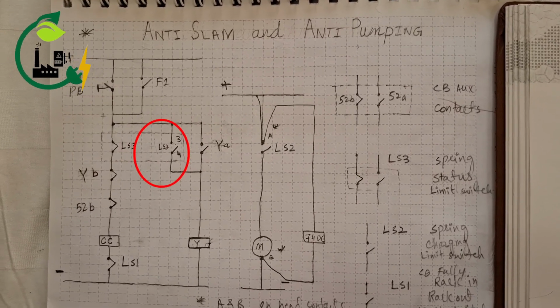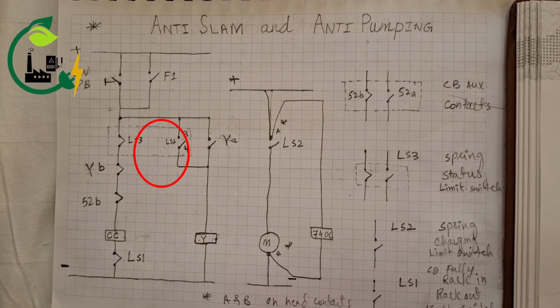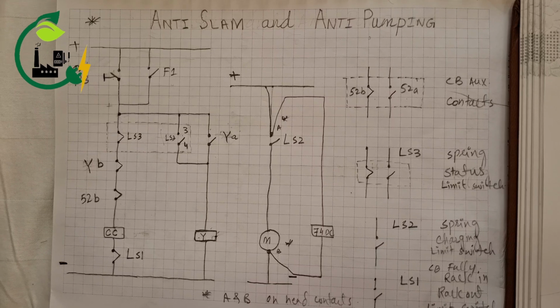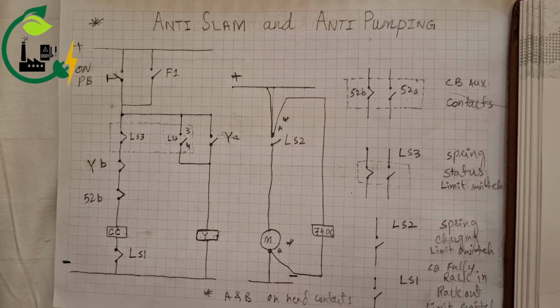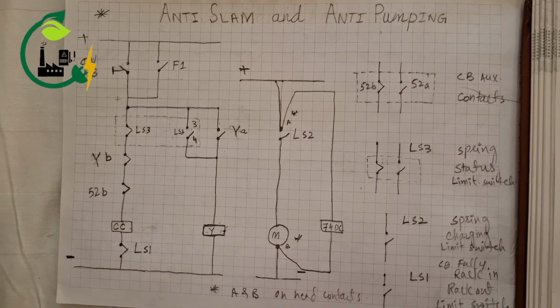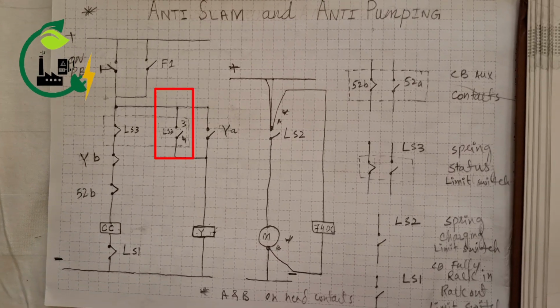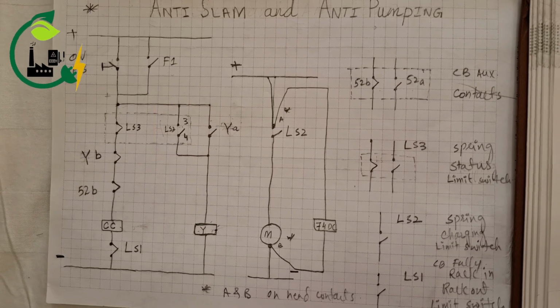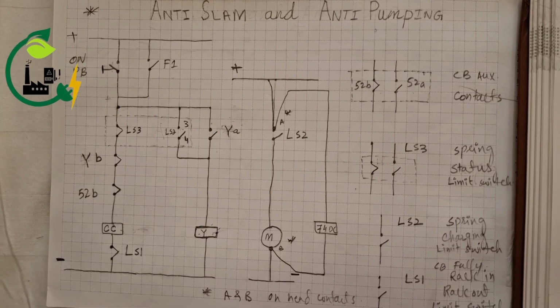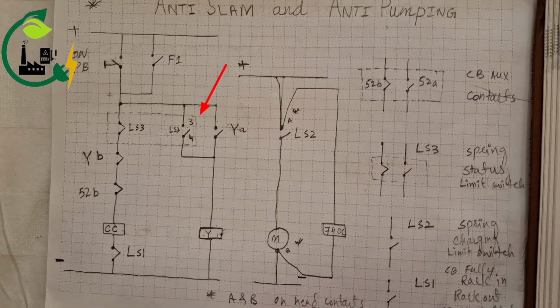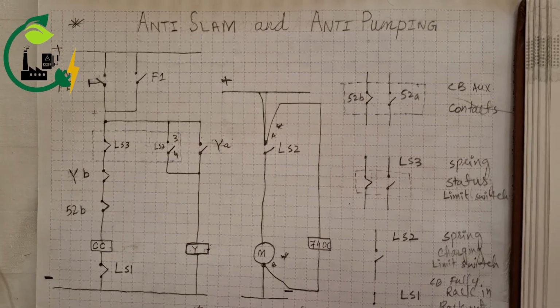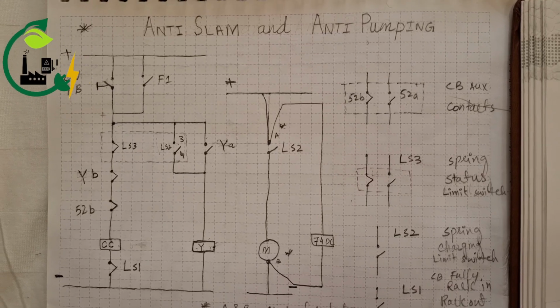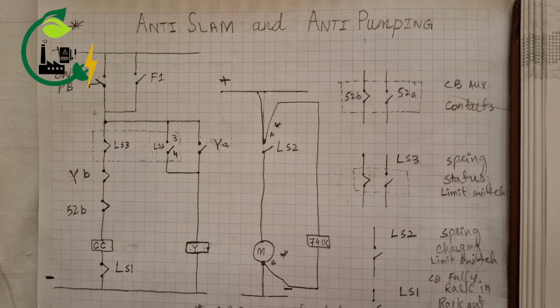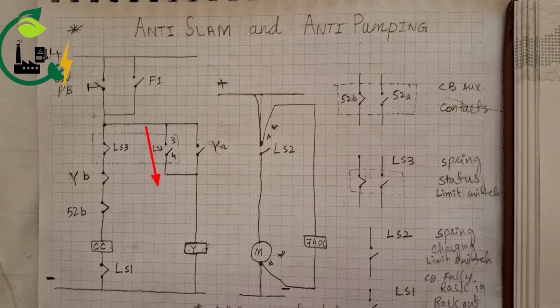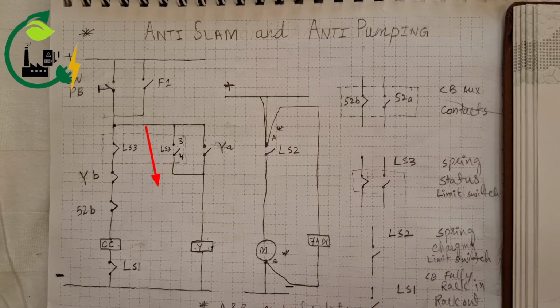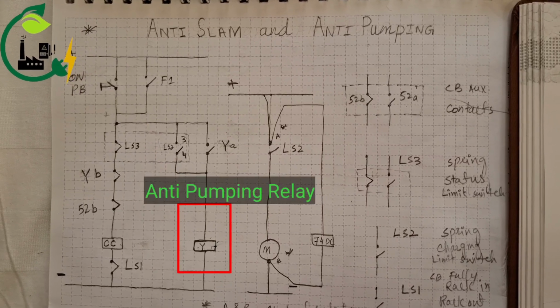The LS3 3-4 contact closes when the spring is discharged, and when the spring is charged it becomes normally open. So when the circuit breaker is open, the spring is fully charged and this contact 3-4 will be open. What we need is that once the spring is discharged, this 3-4 contact of LS3 should be closed. So once we give a command to the circuit breaker, the spring becomes discharged. First the command goes to the circuit breaker coil, and at the same moment, once the spring is discharged, the LS3 contact 3-4 will close and give supply to the anti-pumping relay.